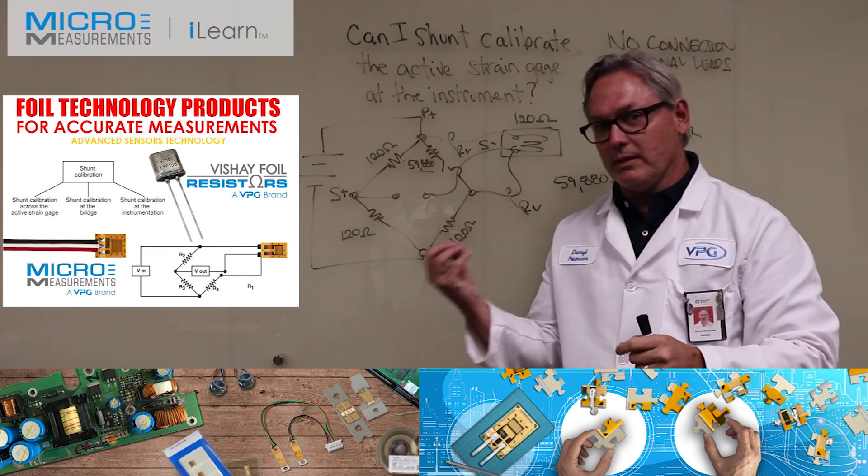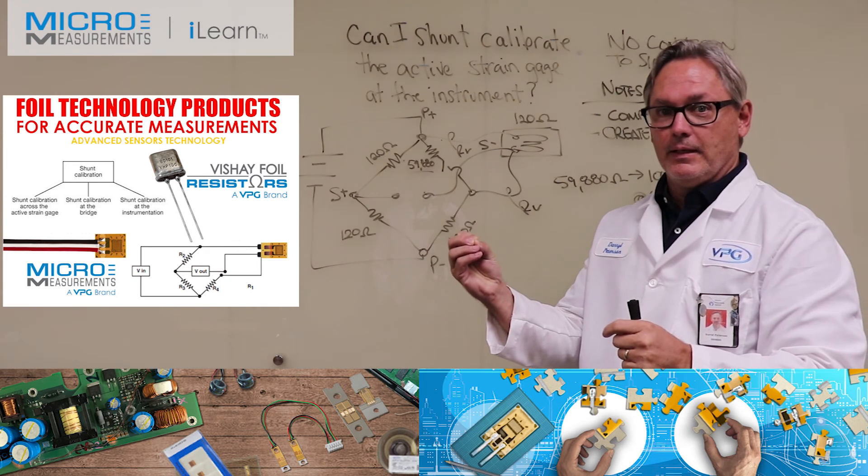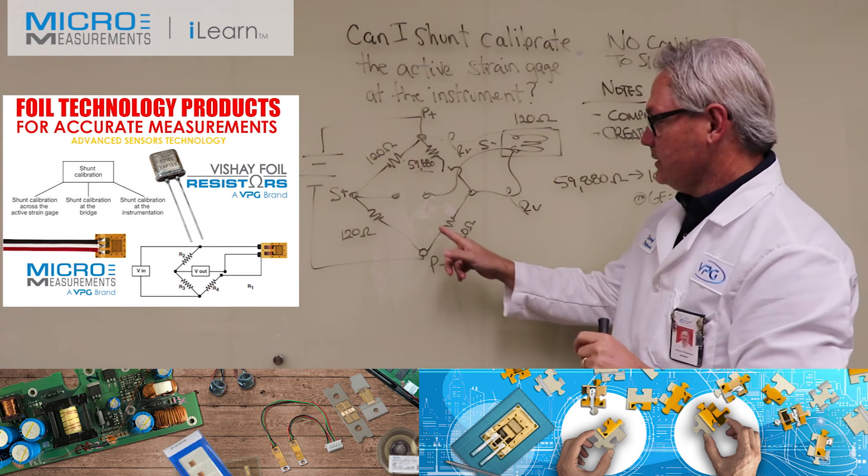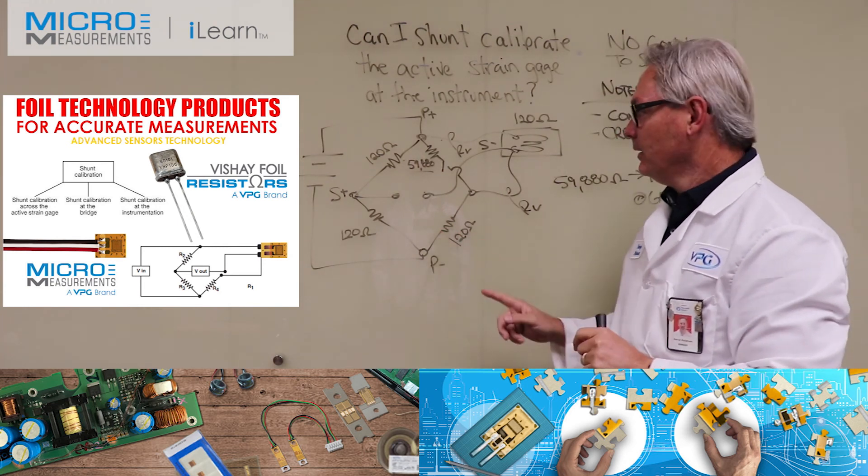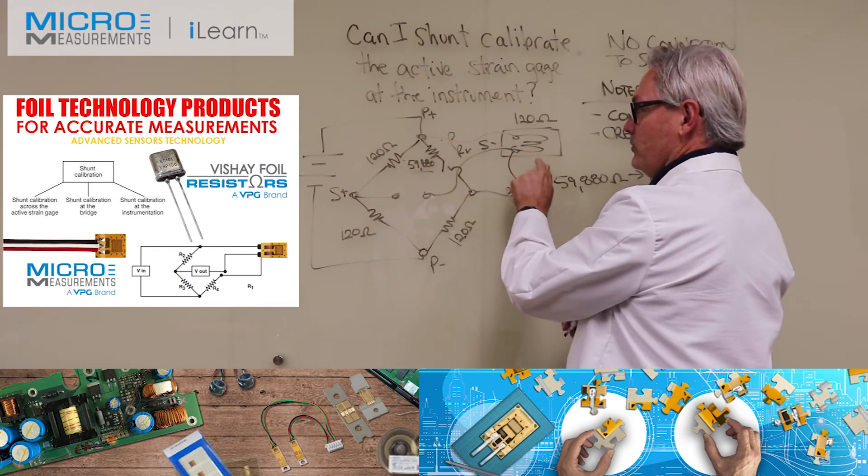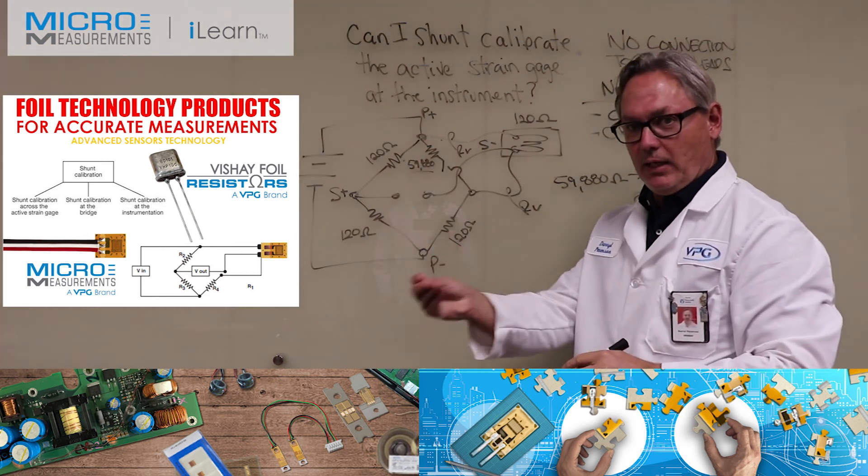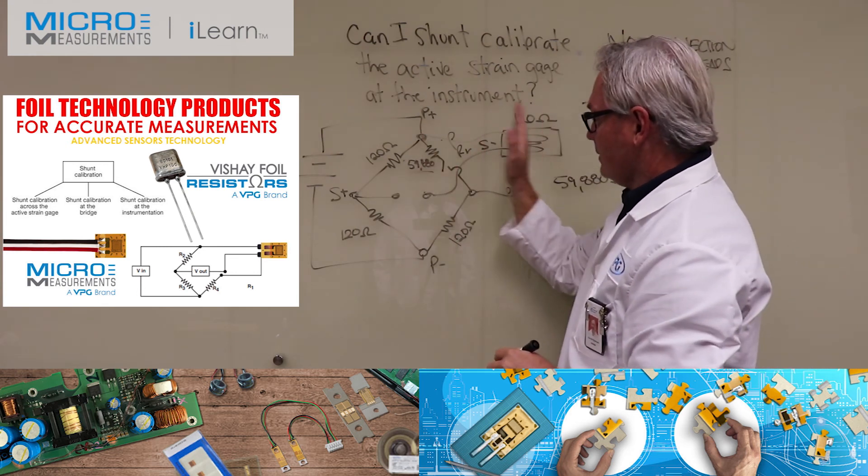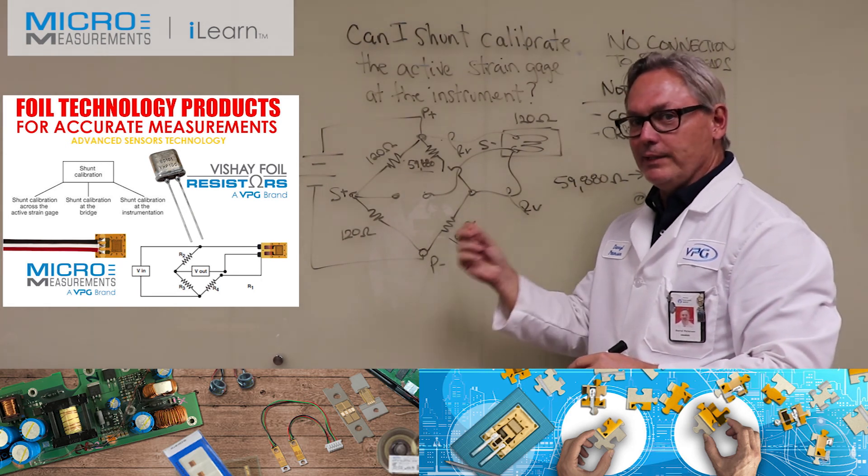Depending on what that value is, that will throw off your calibration. If you remember from the previous videos, one of the things we like to do is calibrate across a very precise resistor. In general, your lead wires are not going to be anywhere near as precise as these 0.01% bridge completion resistors. So if you knew the resistor values of R_cable and you took that into account when you're calculating this parallel resistance, then maybe you can calibrate the strain gauge.